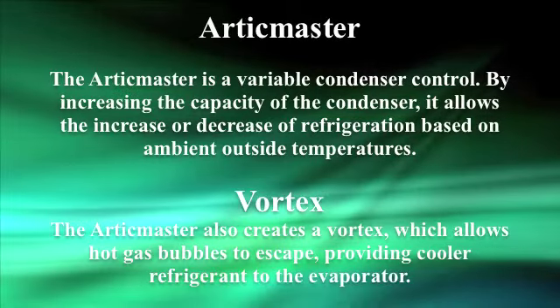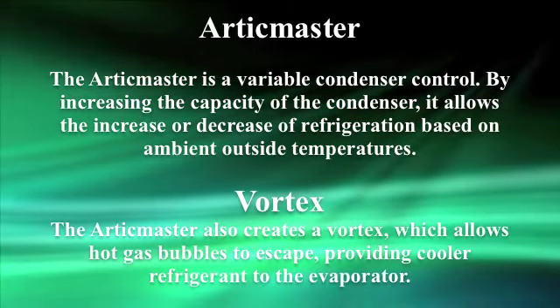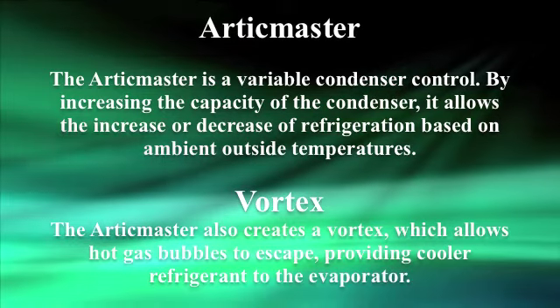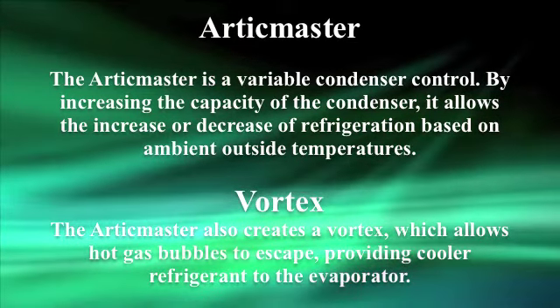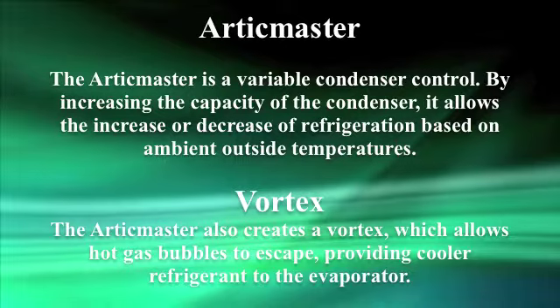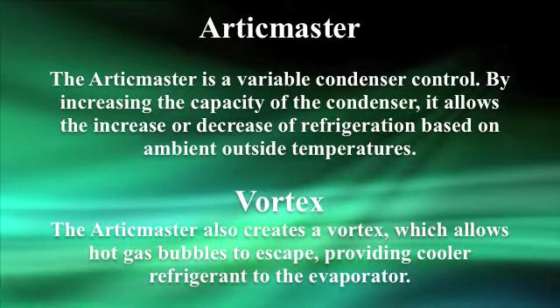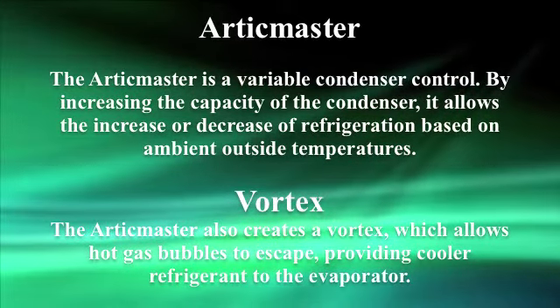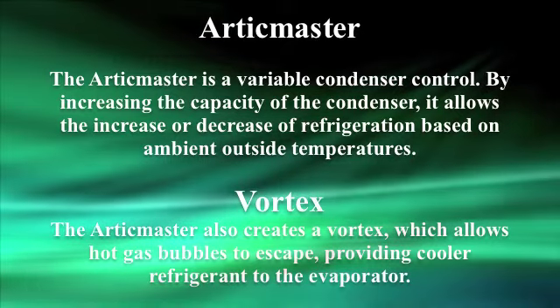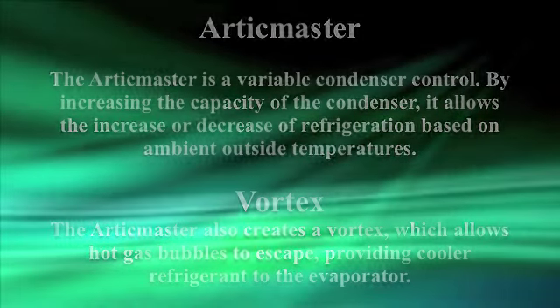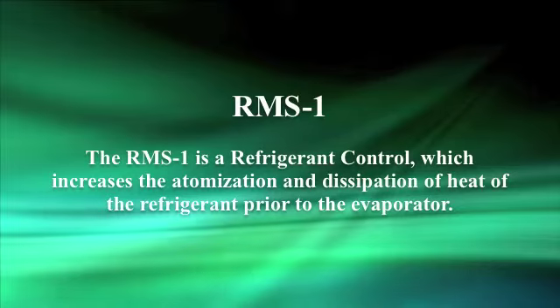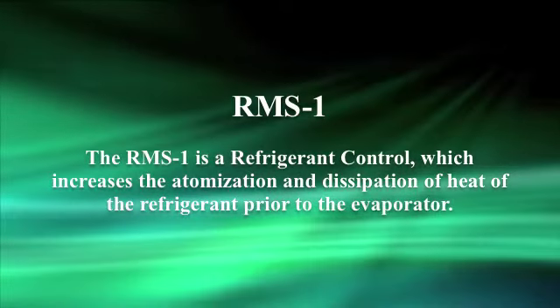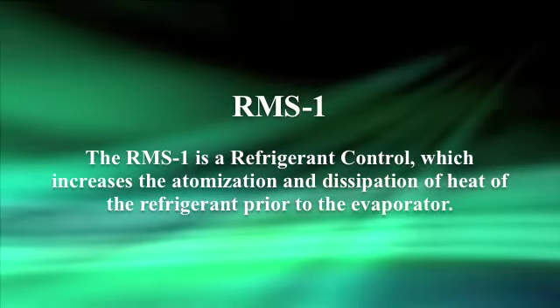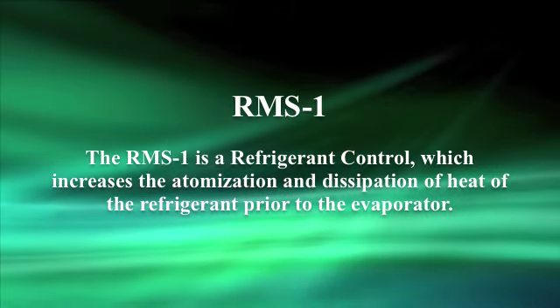The Articmaster is a variable condenser control. By increasing the capacity of the condenser, it allows the increase or decrease of refrigeration based on ambient outside temperatures. The Articmaster also creates a vortex which allows hot gas bubbles to escape, providing cooler refrigerant to the evaporator. The RMS-1 is a refrigerant control which increases the atomization and dissipation of heat of the refrigerant prior to the evaporator.